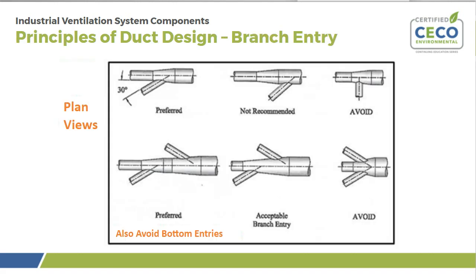Branch entries. Whenever you have a system, you're going to have, most of the time, multiple lines coming in. The top left is preferred. That's what we term as a T-on taper fitting, where the 2 smaller diameters equal the larger diameter going out. That blends the air in the most effective manner and lessens the chance of material falling out. Top center is not recommended, because in that taper section, the air is actually slowing down. You want to avoid that straight 90-degree tap in, because again, if it's an abrasive material, over time it's going to blow a hole in the top of that taper section.